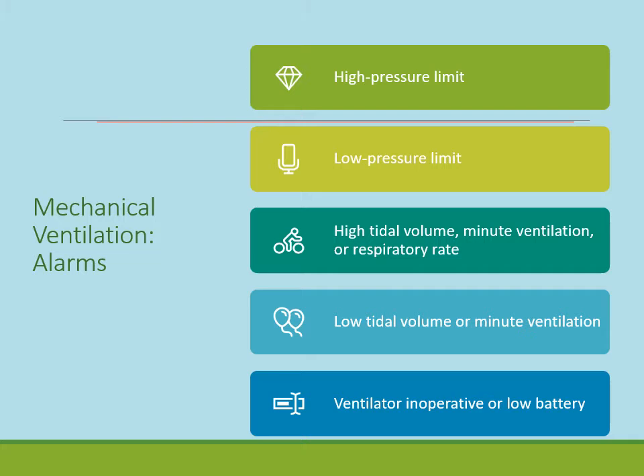An apnea alarm can be triggered for respiratory arrest, oversedation, change in patient condition, or loss of an airway. A high tidal volume or minute ventilation or respiratory rate alarm can be triggered for patient condition or excessive condensation in the tube. Low tidal volume or minute ventilation alarm can be triggered for a change in the patient's breathing effort, such as the rate or the volume.